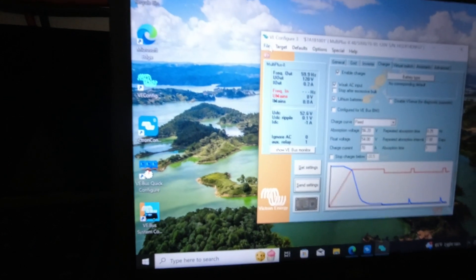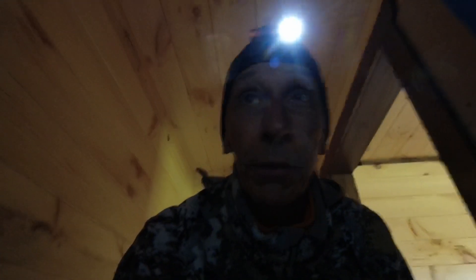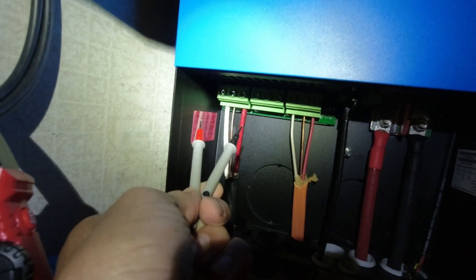The inverters are at 60 Hz, 120 volts, with a little bit of idle consumption. Looks good — all done. We can turn the lights on. I've got to do one final check and measure the voltage between the two inverters. Between the hot and neutral on L1 I get 120V, and between L1 and L2 I should get 240V. Let me go from black to red — 239-point-some volts.